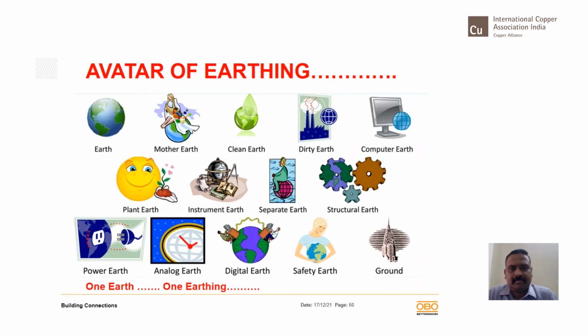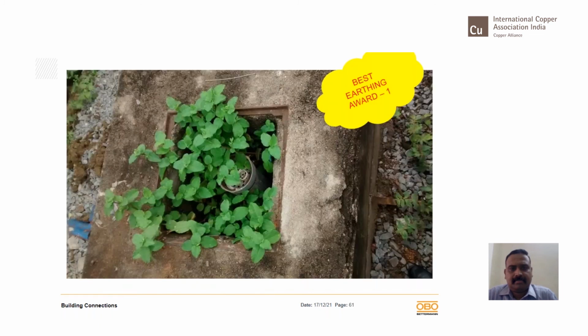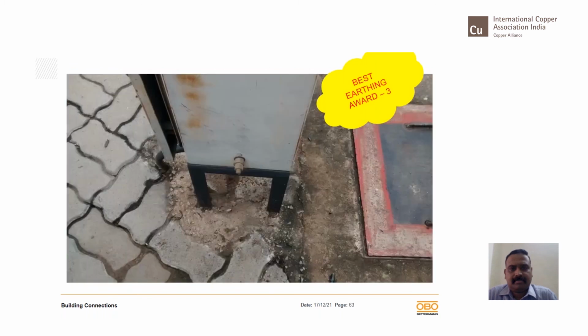It is not insulated. Now, what is more important in implementation of earthing is the good practice of maintaining an earthing. Remember, earth pit is not a tree pot. Earth pit is not a dustbin. Earth pit is not just for the namesake to be placed in that location. You need to have a proper connection. You need to maintain the earth pit more than having an earth pit in place.